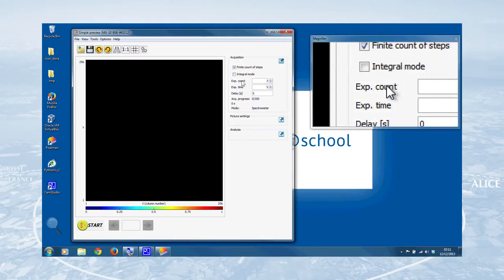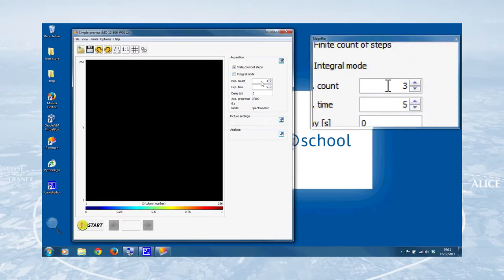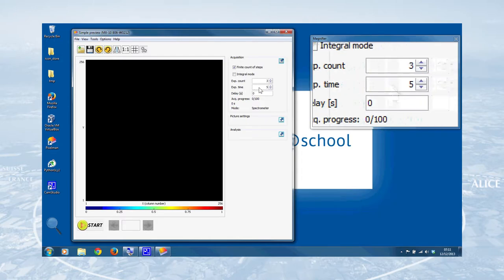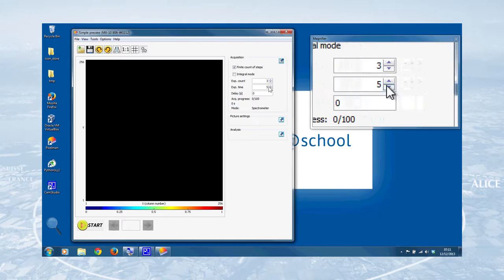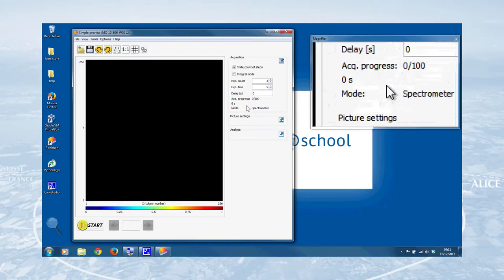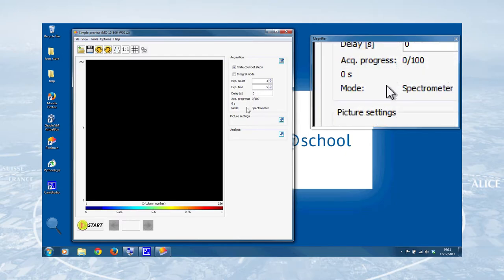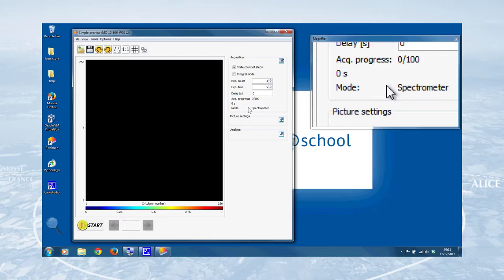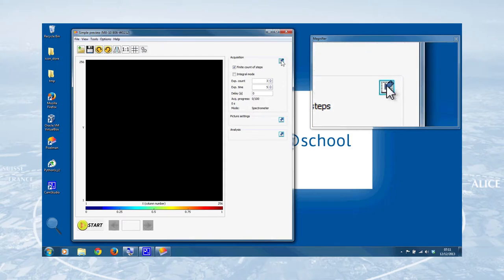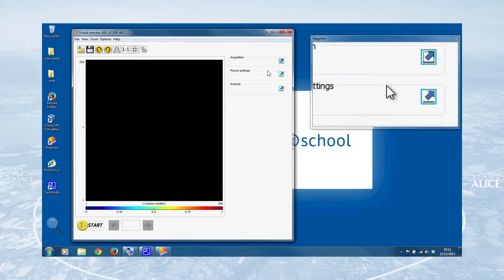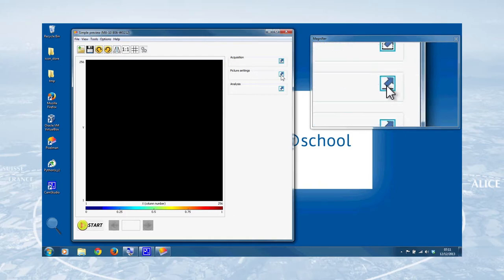The exp count, the experiment count, is the number of frames that the software will take. And the exp time, or the experiment time, is the length of time that each frame will be making a measurement. So here we've got three frames, each of five seconds, that's 15 seconds worth of data. Not very much in the grand scheme of things, but for this simple demonstration, that's just what we want. And finally, just the panel here telling us that we're in spectrometer mode, which means in principle we can make energy measurements of the particles that we detect. So we can leave all that, close that panel by clicking on the bottom button in the top right, and then go to picture settings.